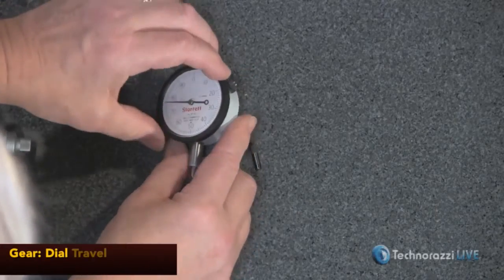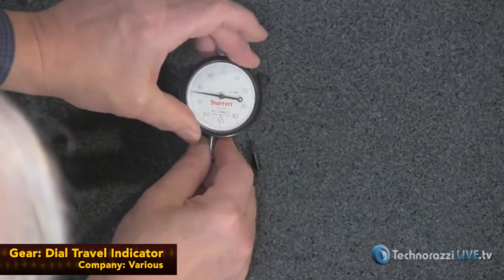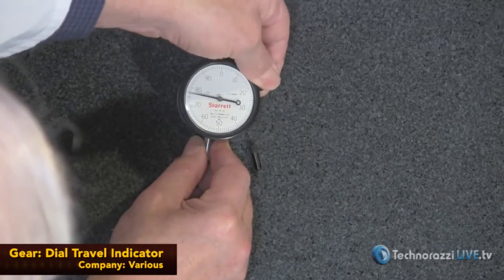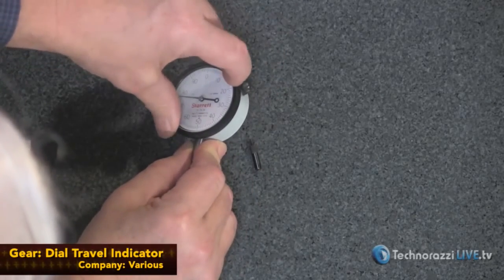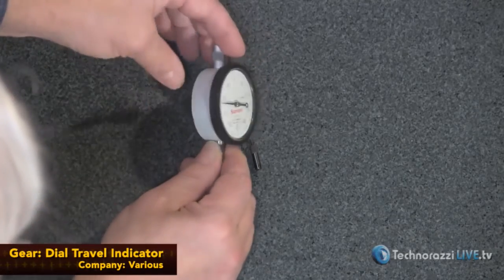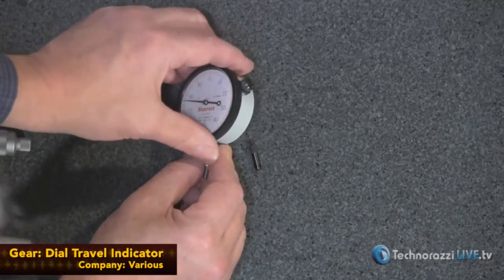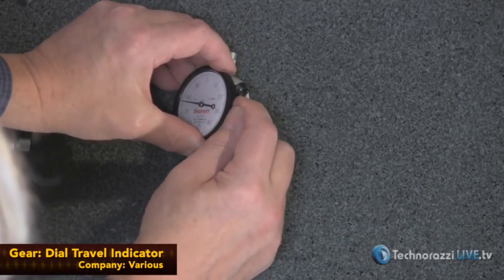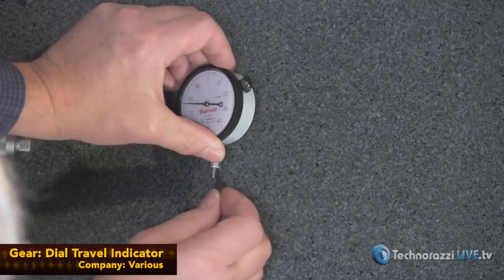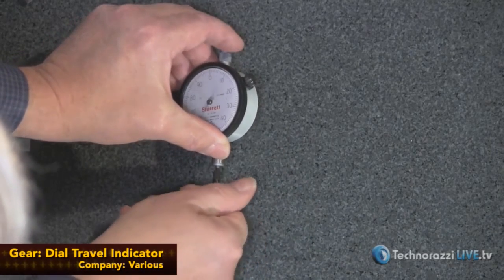These have a clamp which, when loosened, you can rotate the dial, and when tightened, it holds it down. A lot of times these clamps will break. See if there is one. They'll all have a hole in there, but some of them will be missing the clamp. See if the clamp works. Sometimes it's there and it's busted off. So visually, you might think it's working, but it's not actually doing what it's designed to do.